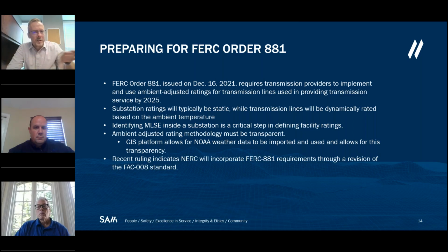Our discussion today has been mostly around substations and measuring equipment inside substations. In terms of rating a facility, a transmission line, your substation is going to be, for the most part, a static rating. Your breakers, your switches, bus sections, they're not going to change based on the ambient temperature. However, you do need to identify the most limiting series element. You need to verify the facility rating as a baseline for your ambient adjusted temperature that will apply to the main conductor that ties the two substations together.